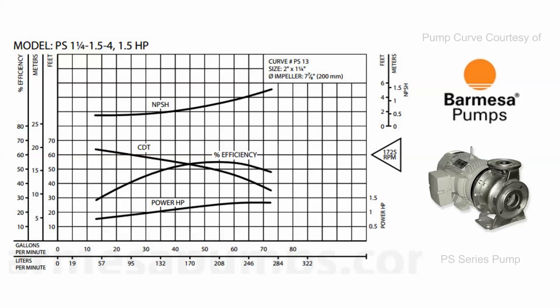This particular pump curve is a great example because you can really see the detail of information offered in one small graph. It shows motor speed at 1725 RPM, horsepower requirements, gallons per minute, liters per minute, efficiency, and head in meters and feet. This pump is offered in one and a half horsepower so it can achieve the full range of the curve without fear of overloading. Additional information includes the curve number for referencing with the manufacturer, size information, and impeller diameter — all giving a person a thorough picture of expected pump performance.